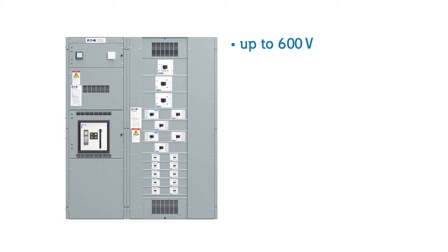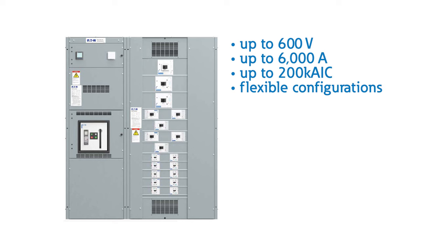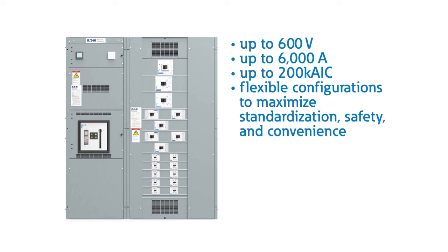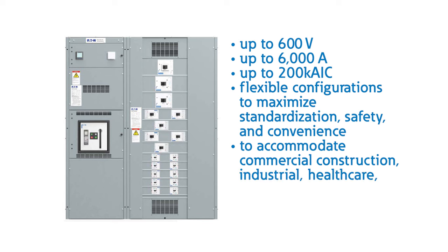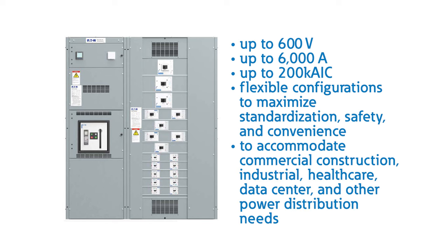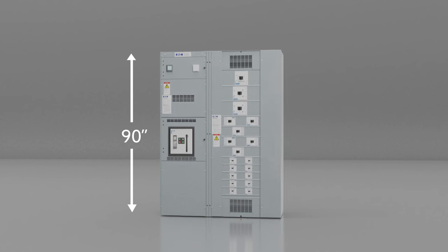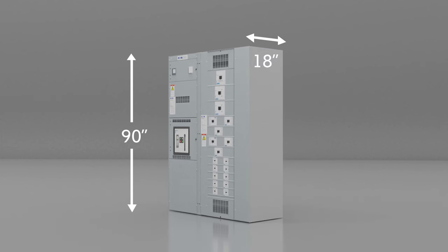Switchboards can range up to 600 volts, 6000 amps, and 200 KAIC, and offer flexible configurations to maximize standardization, safety, and convenience to accommodate commercial construction, industrial, healthcare, data center, and other power distribution needs. Switchboards are typically 90 inches tall with a minimum depth of 18 inches.